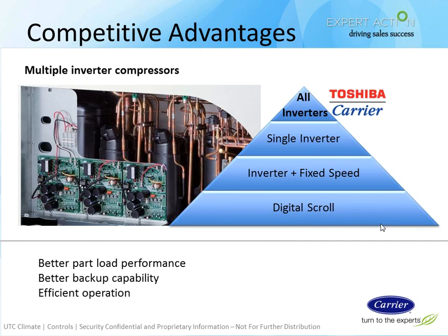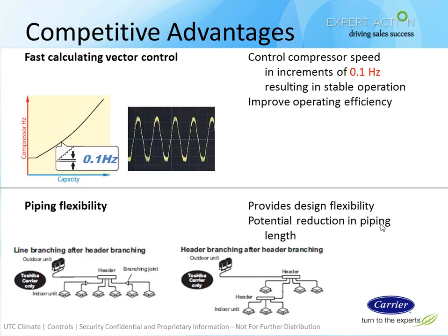So if the zones calling for cooling or heating require only one compressor to run at about 80%, it will run to that level. And then additional compressors will be brought on as needed. That provides better part load performance, gives you better backup capability, and more efficient operation. The response of the compressors to calls for heating or cooling is very quick and in very small increments. This gives you nice, quiet ramp up of the compressor, so it's very quiet heat, a very quiet cooling.